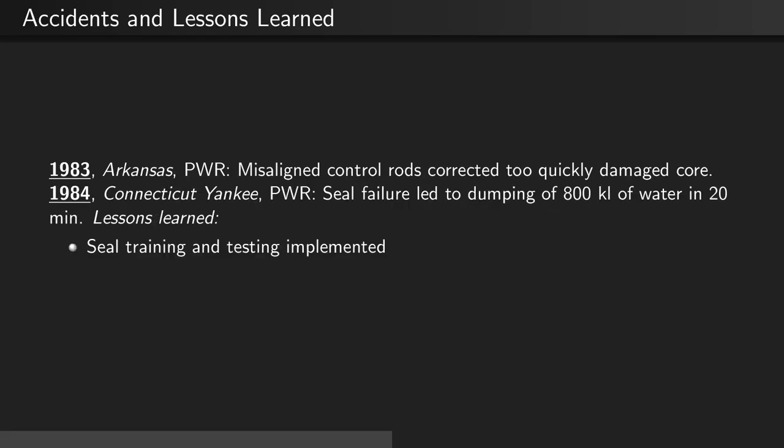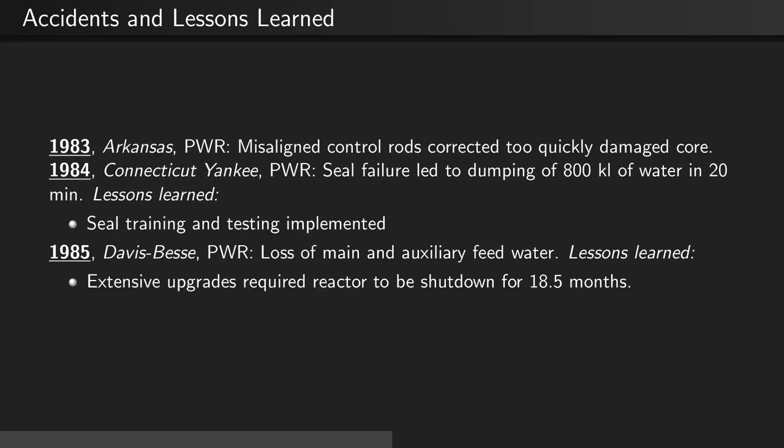In 1984, at Connecticut Yankee, again a PWR, there was a seal failure which led to the dumping of 800 kiloliters of water inside of 20 minutes. This led to seal training and testing implemented across PWRs. In 1985, we returned to Davis-Besse, where there was a loss of main and auxiliary feed water. This led to extensive upgrades, requiring the reactor to be shut down for 18 and a half months.